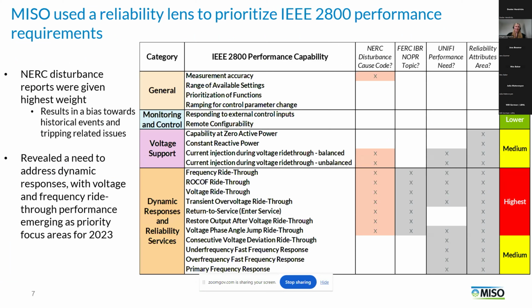So there were a lot of gaps identified, and as we've already heard from Wes's presentation, the clauses in the 2800 standard do have a lot of complexity. So instead of trying to adopt them all at once, we decided to do this over multiple phases. So it was necessary to prioritize which capabilities should be in each phase. Really wanting to emphasize reliability as we did this, we used the NERC disturbance reports as our primary source for prioritizing which 2800 requirements to adopt first.